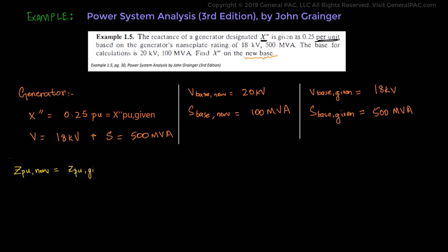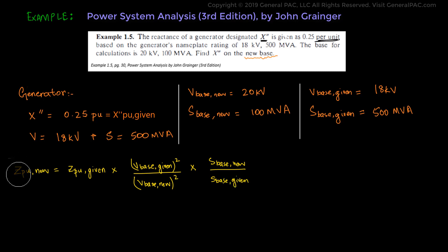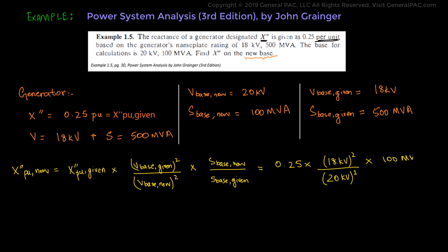The formula is: Z per unit new equals Z per unit given times V base given squared divided by V base new squared, times S base new over S base given. Equivalently, X double prime per unit new equals X double prime per unit given times V base given squared over V base new squared, times S base new over S base given. Entering the values: X double prime per unit new equals 0.25 times (18 kV)² over (20 kV)² times 100 MVA over 500 MVA, which equals 0.25 times 0.81 times 0.2, giving 0.0405 per unit.